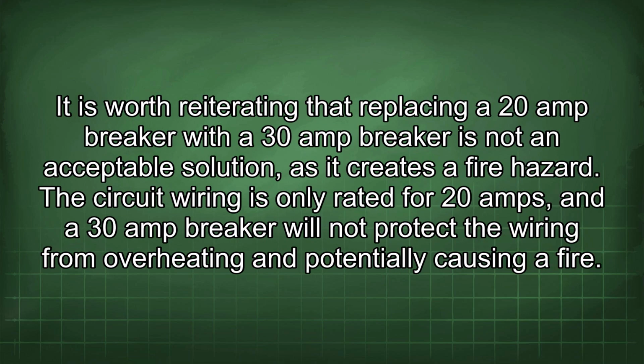It is worth reiterating that replacing a 20 amp breaker with a 30 amp breaker is not an acceptable solution, as it creates a fire hazard. The circuit wiring is only rated for 20 amps, and a 30 amp breaker will not protect the wiring from overheating and potentially causing a fire.